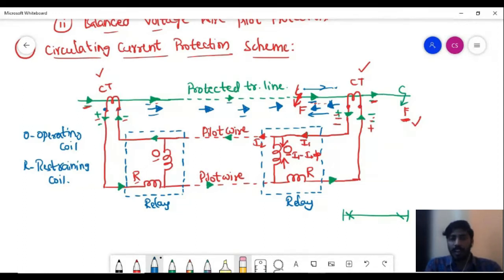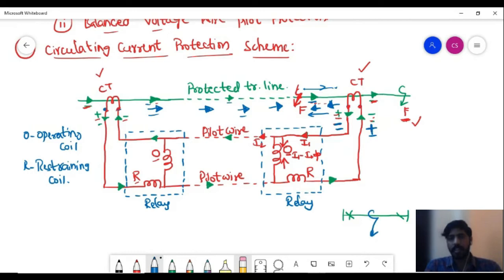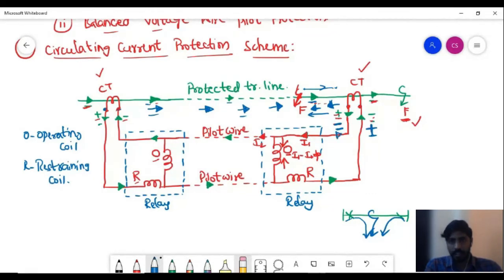When the direction of current is reversed, the polarity of the CT secondary at the remote end also gets reversed — this terminal becomes minus and the other becomes plus. This reversal of CT terminals at the remote end occurs because the current is trying to feed the fault. So when a fault takes place, the current direction feeding to the fault causes the receiving end CT polarity to reverse, and consequently the current direction through the secondary circuit is also reversed.